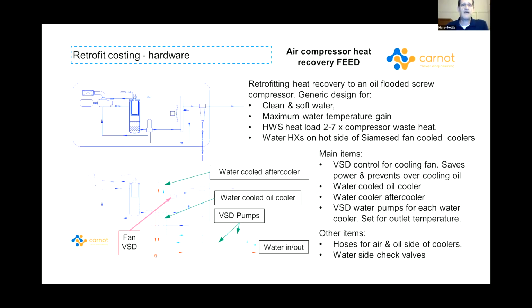We've heard from Jensen about the need to have split systems. We've got variable heat loads in the oil cooler and the after cooler, so run variable speed pumps that are controlled on the temperature coming out of those coolers. You give the heat recovery system the first grab at the water. You run nice slow water flows through it, so you get maximum temperature rise. You tell the pumps what temperature you want to come out, and they run at that speed to give you that water. If you're getting too greedy and going too high, the fan will run. You'll get your hot water, but maybe not all of the heat.